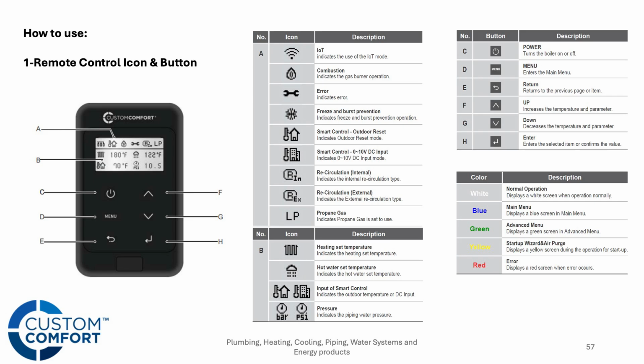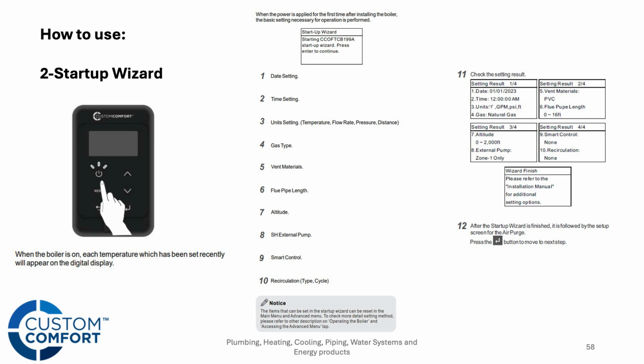And we do that via Startup Wizard, right? So the programming on this, we're going to walk you right through it. It's as basic as setting the date and time to start with, but then going a little bit deeper and really getting into some of those parameters. Again, like we talked about before, it's going to come natural gas out of the box. It's a super easy conversion with the propane kit. We do need to tell the boiler what fuel is being fired though, right? So that's going to come into that Startup Wizard.